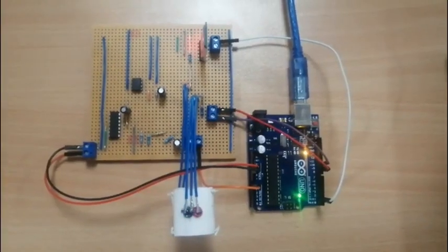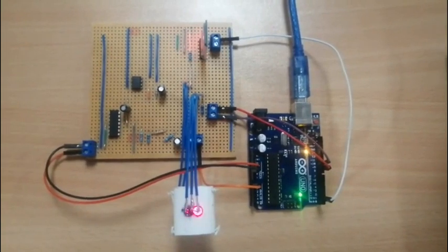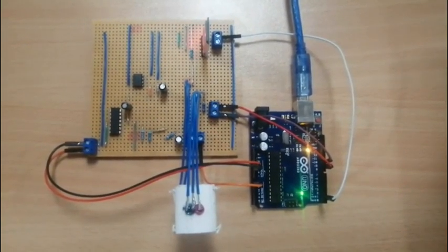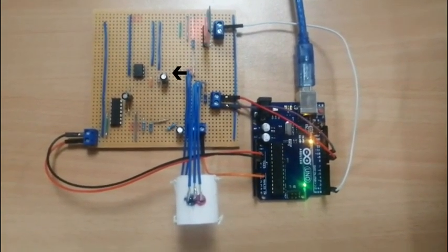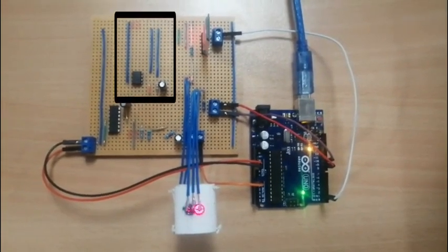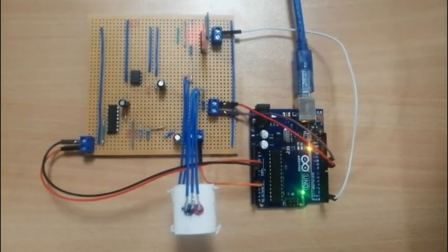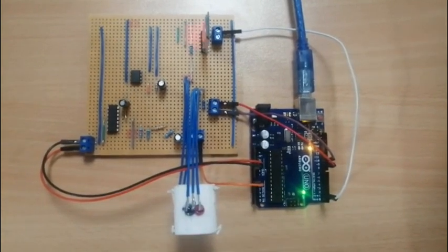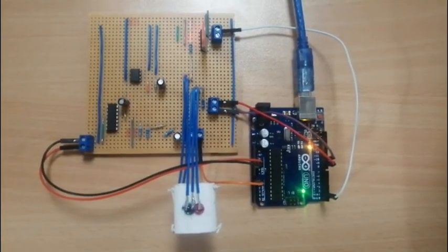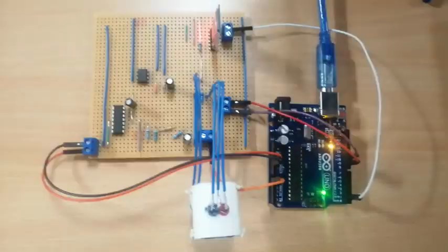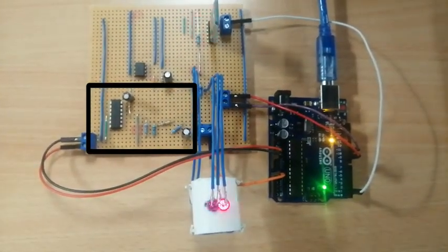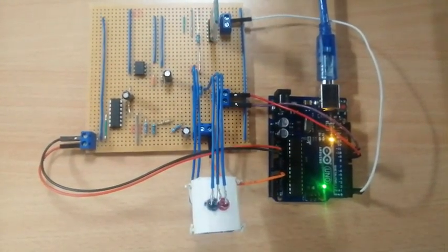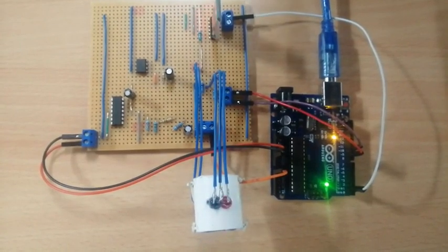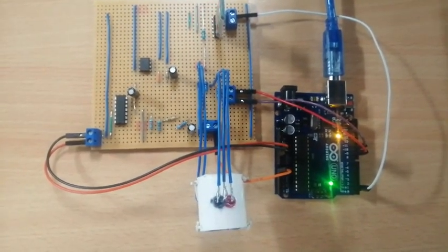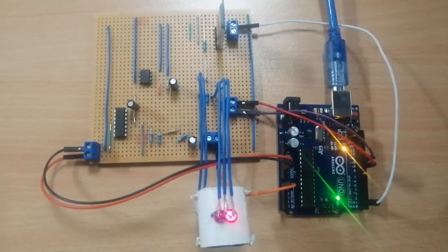So the output from the photodiode is a really small current corresponding to the amount of light detected. The output current is fed to a transimpedance circuit which converts the current to a voltage and amplifies the voltage. The amplified voltage goes through the filter, which is the next stage. The bandpass filter filters out frequencies below 0.8 Hz and greater than 5 Hz and further amplifies the voltage signal. The output signal from the bandpass filter is then fed to the microcontroller.